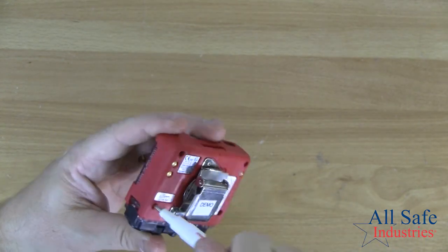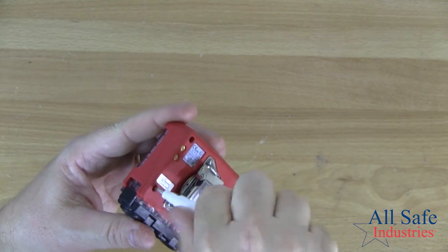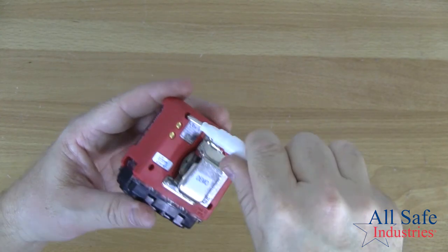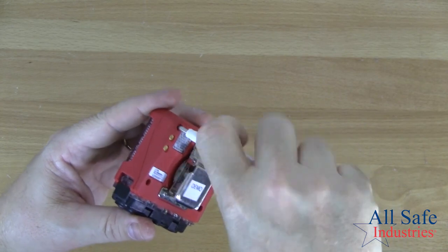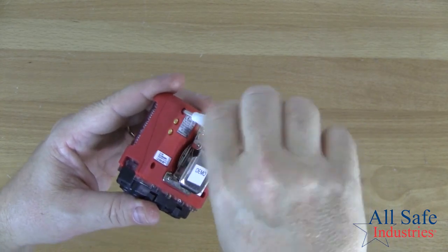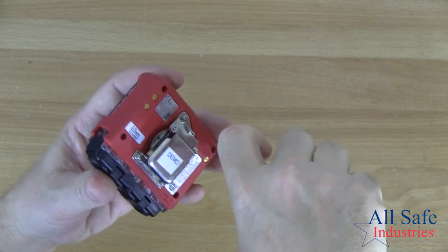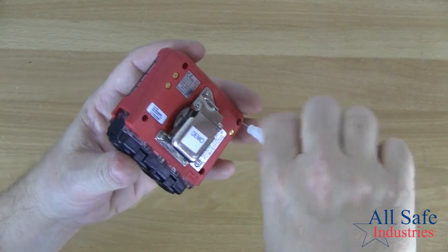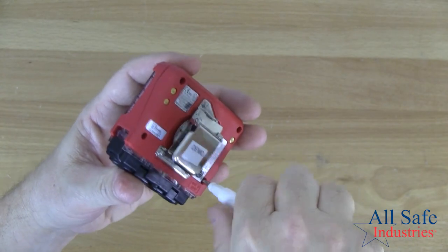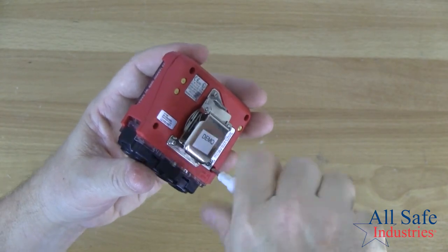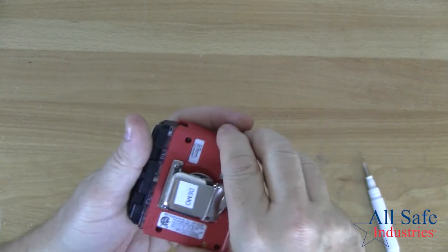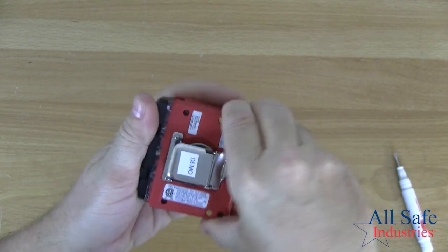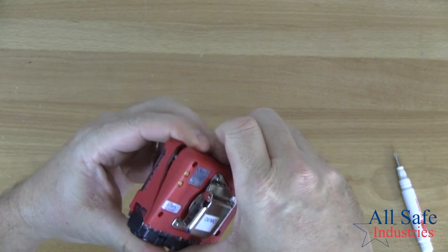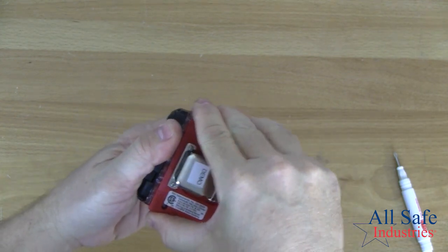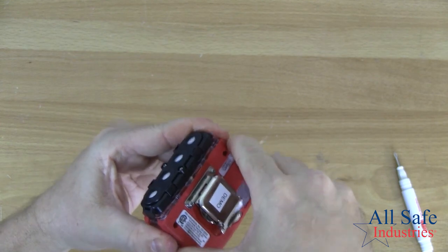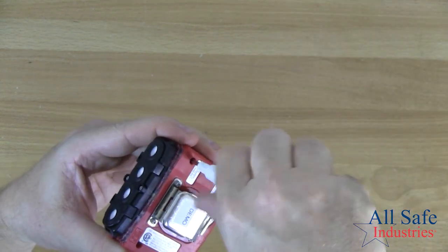Let me show you one other way we would take this apart, and that is if we wanted to change our batteries. Now these are rechargeable nickel metal hydride batteries. We have not seen a lot of customers changing these out, so they should last a long time. But if you're noticing that you're not getting a 20-hour runtime off the batteries that are installed, worst case scenario, your meter goes to full charge and then it will only run for 2 or 3 hours. It might be time to change those batteries. So you loosen those 4 screws, and then this whole back cover plate is going to come off. You've got to make sure that all the screws are fully loosened for that to release.